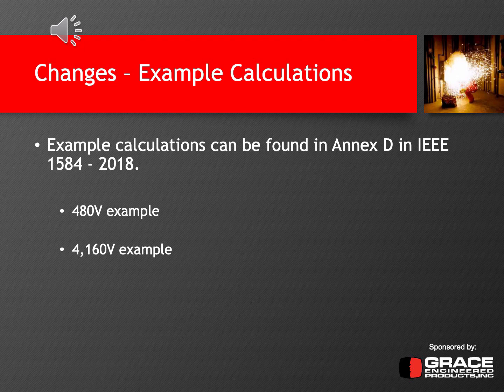And if you're looking for examples on calculations, the 1584 2018 edition, Annex D, D as in dog, has 2 different examples. There's a 480 volt example, which runs through the inputs, then goes through each calculation, and then makes determinations on what the incident energy would be. And then there's also an example for 4.16 kV or 4160 volts. That example goes through a medium voltage example as well. So those are 2 very important calculation examples that allow you to follow the steps that I just covered from steps 1 through 5, and allow you to see what was included and where they got the data from.